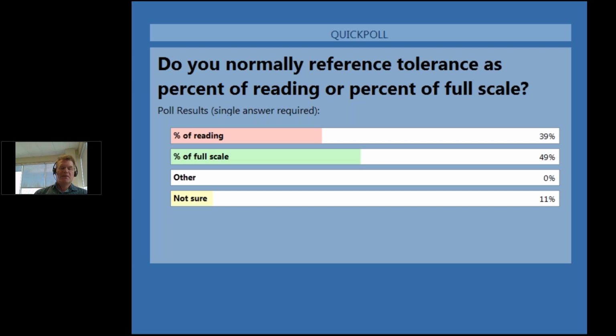Be aware of the difference, right? Full scale means if you have a 0 to 100% range, 1% accuracy means you'll get no greater resolution than 1%. If it's percent of reading and you're reading 10%, with 1% accuracy, then you're down to 0.1%, right? An order of magnitude difference. So be aware of that when you're specifying and buying your instruments as well.